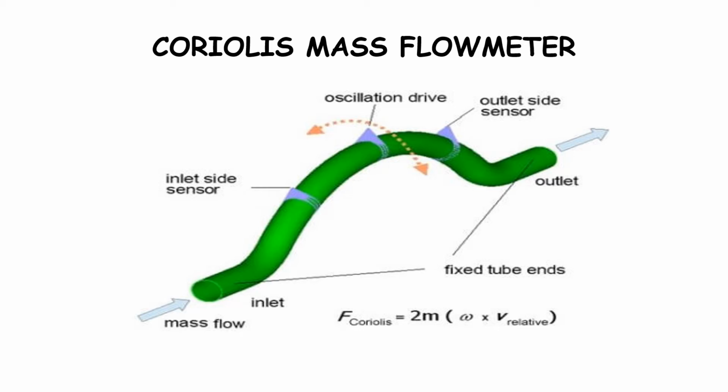Both U as well as omega-shaped Coriolis meters cause pressure drop as the flow is increased, resulting in a permanent pressure loss. Consequently, liquids near the boiling point could introduce cavitation as the pressure across the meter drops below the vapor pressure of the liquid. As soon as the pressure recovers above the vapor pressure, the bubbles implode. Now the cavitation will cause the meter to malfunction, and this must be avoided at all times.